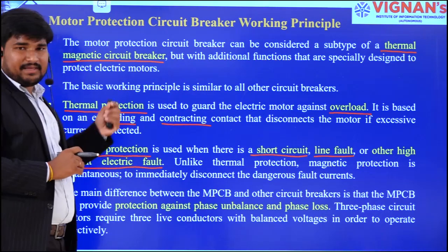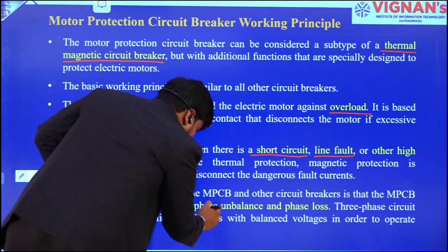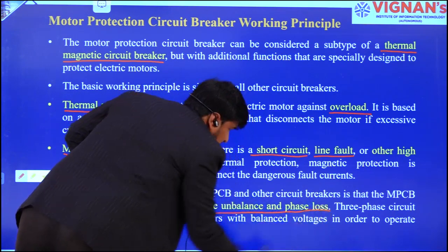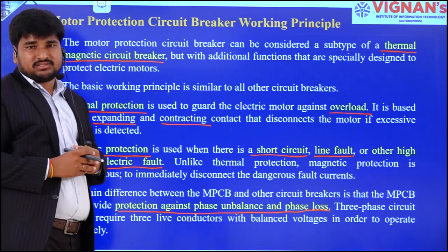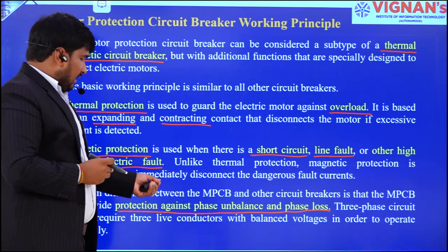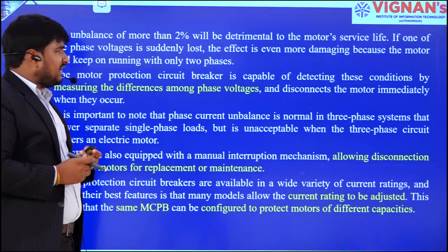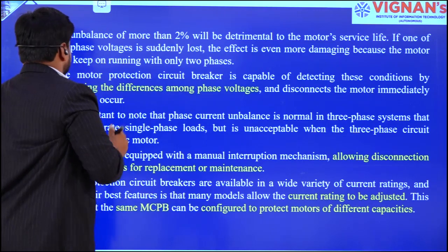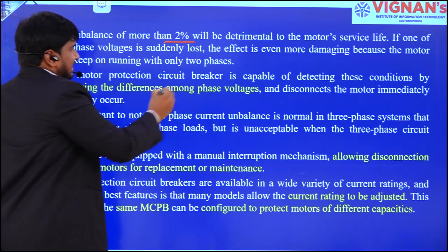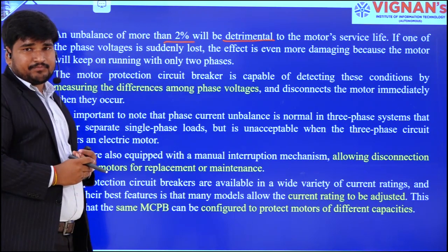But in the case of MPCB, that is motor protection circuit breaker, we have one more protection additionally, that is protection against unbalances and phase loss. During phase loss or unbalances, if there is even 2% unbalance, it will be detrimental to the motor service life, right?